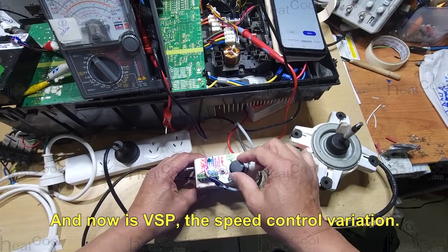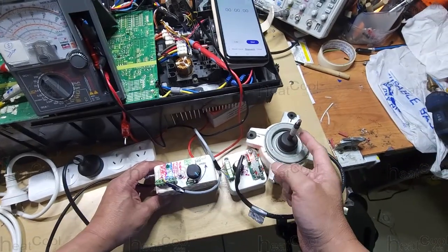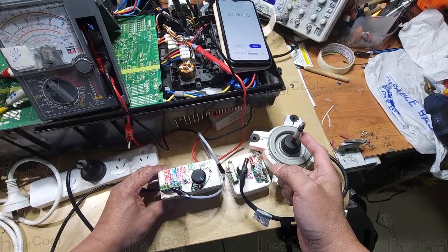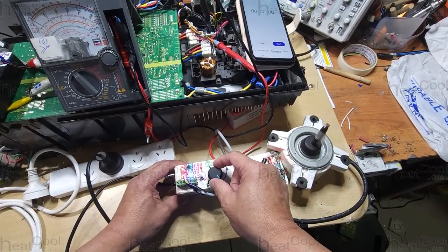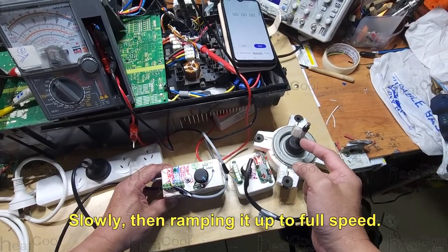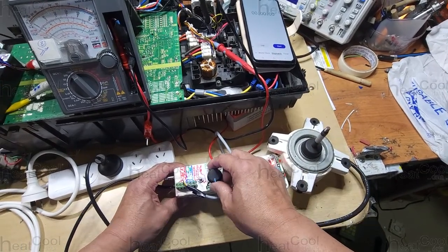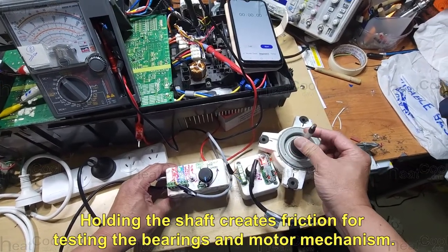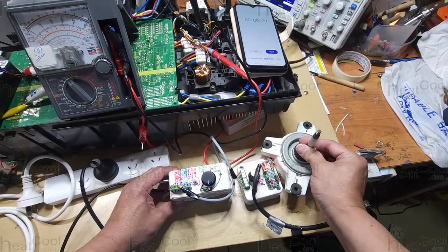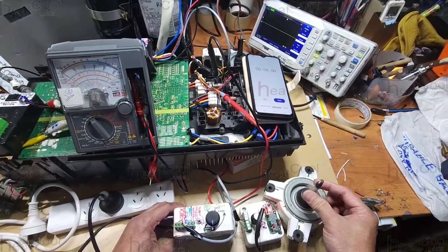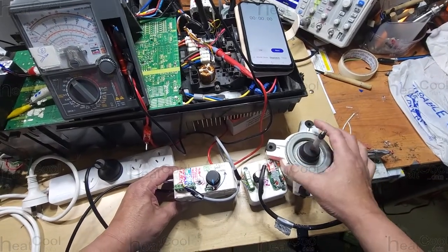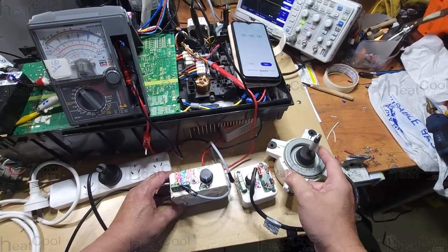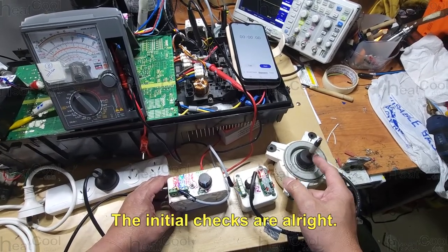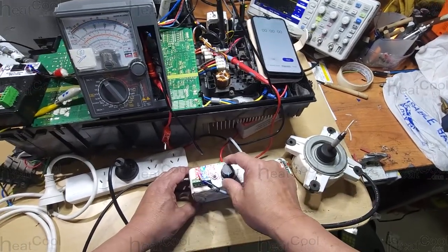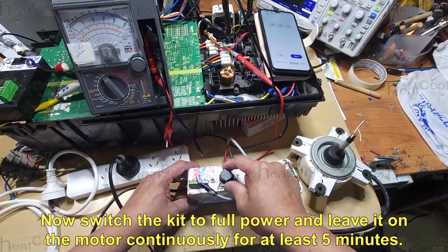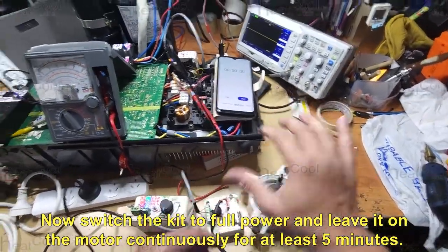And now is VSP, the speed control variation. Slowly, then ramping up to full speed. Holding the shaft creates friction for testing the bearings and motor mechanism. The initial checks are alright. Set it to full power and leave it on the motor continuously for at least 5 minutes.